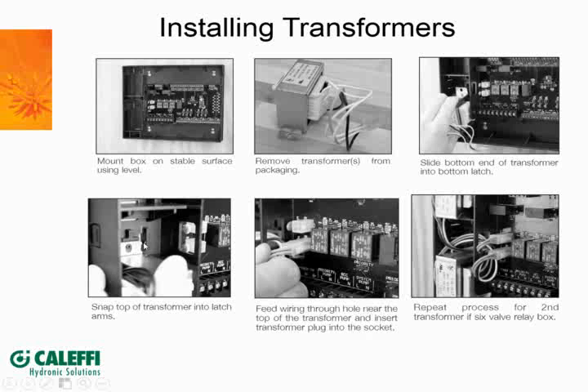Yeah, and like Bob said, you can spread these snap arms right here to remove it. It's not the easiest thing, but you certainly can do it. You kind of have to move one tab, pull the transformer over a little bit, and then move the second tab. Unless you got some type of spreader wrench, like a Truarc, that you could pull open and spread them both at the same time. But it certainly can be done. It's better than drilling out rivets, that's for sure. Yeah, it's not hard to do. And you know what else would work is snap ring pliers, the kind where you squeeze them and the 2 fingers spread out sideways. That would just open it too.